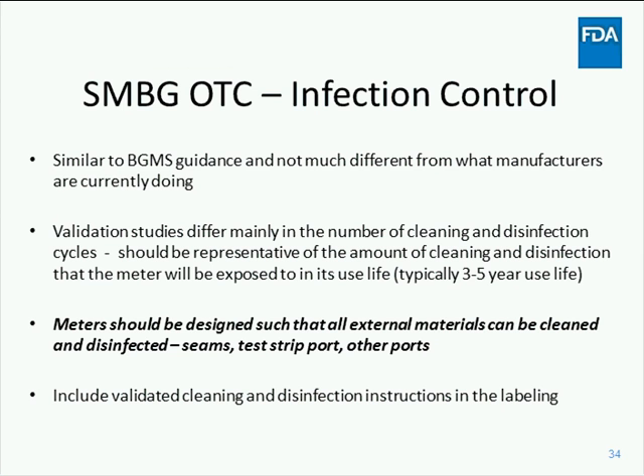Similarly, the infection control studies are very similar in this document as described in the BGMS document. The validation studies are based on expected use and the use life of the device. Therefore, the single patient use devices will typically have fewer validation cycles for the robustness study to support the device use life. But as with the BGMS guidance, the over-the-counter meters should be designed so that all external materials can be cleaned and disinfected, and this includes the test port. The validated cleaning and disinfection instructions should be included in the labeling in language that is easily understood by home users.